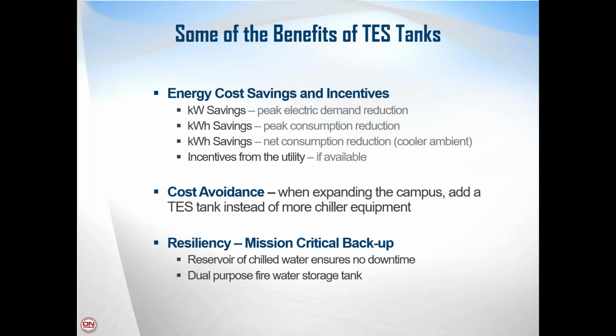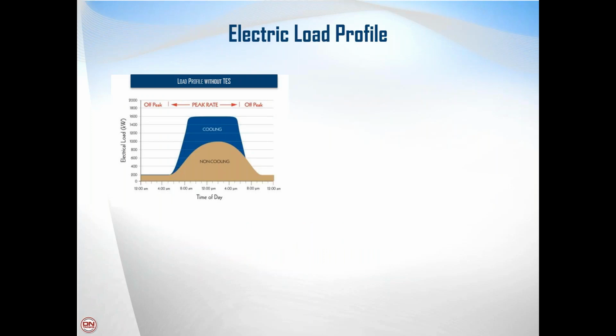The last thing on this particular slide is resiliency. By adding a thermal storage tank to a campus, the owner is getting the fringe benefit of this very large reservoir of chilled water now on campus that could be used for backing up their cooling system in case their chillers go offline unexpectedly, or the tank could be used as a dual purpose tank where the cold water in the tank could be used to help put out a fire in case that were the case at the campus. So those are some of the benefits of thermal energy storage.